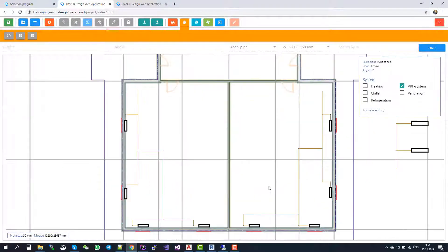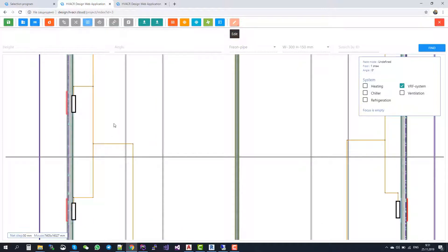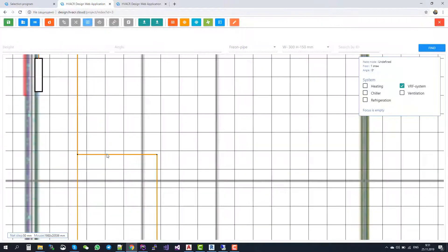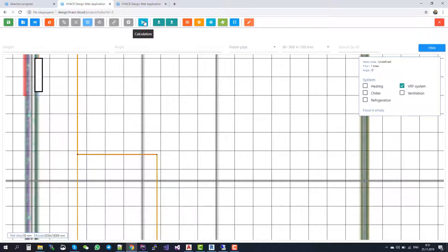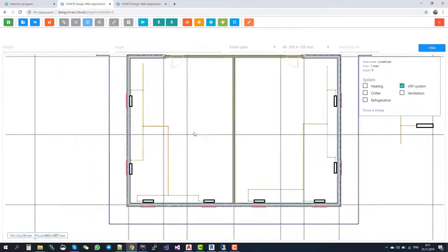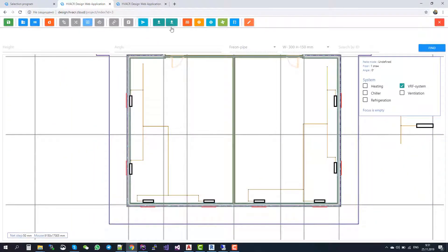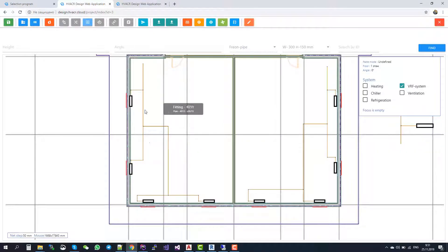When your design is finished, you just select any pipe or any part of the system. And here the calculation button appears. You press this button and the calculation of the whole system starts. For VRF systems, the calculation automatically selects the sizes of the pipes and it also automatically selects the branch joints.